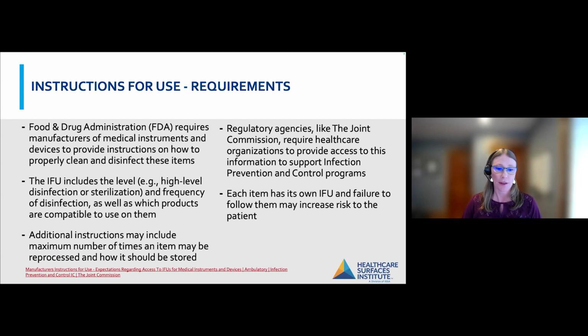So when we're thinking about long-term and needing to purchase new products to replace those, you have to be thinking about that. You also have to be thinking about how you are going to track that. How are you going to keep track of which number of reprocessing you're on for that specific product? Another common instrumentation that has a similar limit on the number of times it can be reprocessed is our robotic surgery instrumentation, and it can only be reprocessed 10 times. So that's just something to add another layer of complexity.